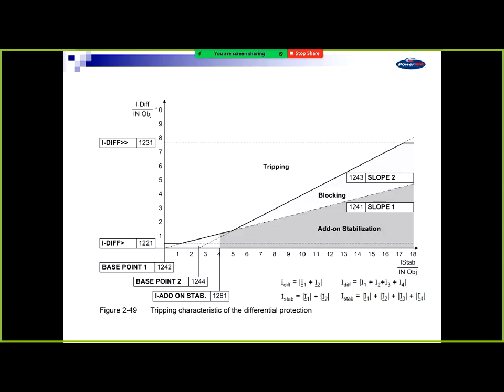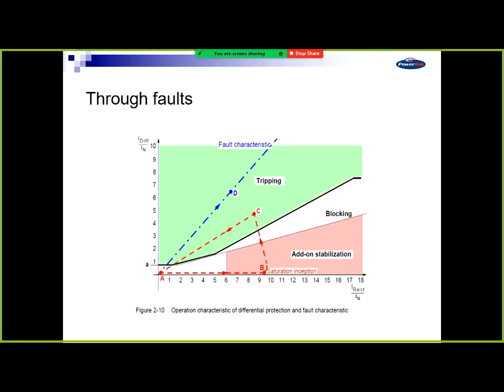I'm not going to do any filtering, compensation or anything. I'm going to trip. So that's how you can get an extra 5 or 10 milliseconds in speed, by not going through the filtering. The problem with that is if you do it at too low a level, you can trip for things that you haven't filtered on, which may destabilise your bias. So setting that, you have to be careful and confident, and we do set it like that.